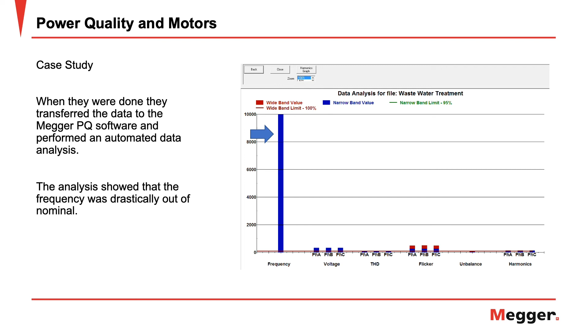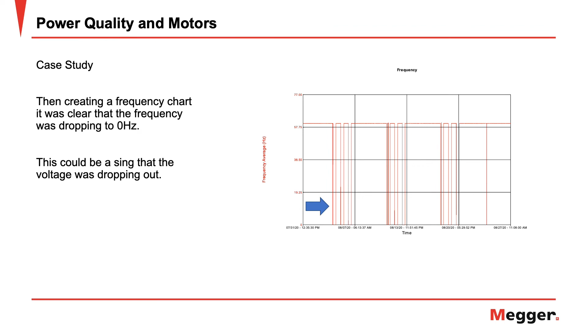Upon seeing this, a frequency chart was created, and it could be seen that the frequency was dropping to 0 Hertz at times. Now, this could be an indicator that perhaps the voltage was actually dropping out. So at this point, we created a voltage trend. It was clear from the voltage trend that the voltage wasn't dropping out.